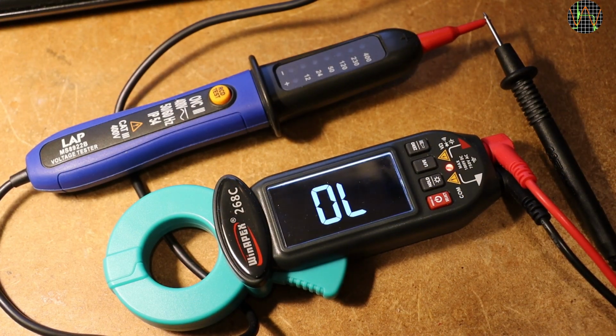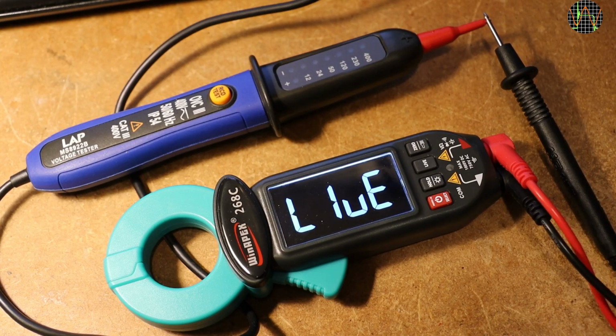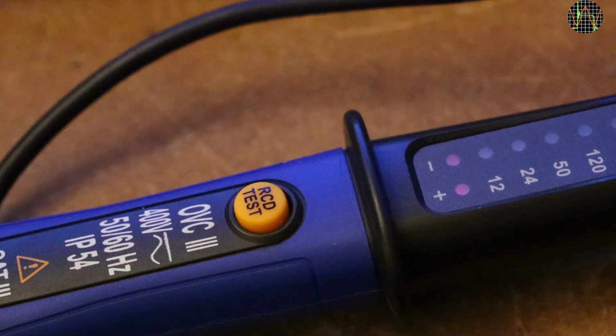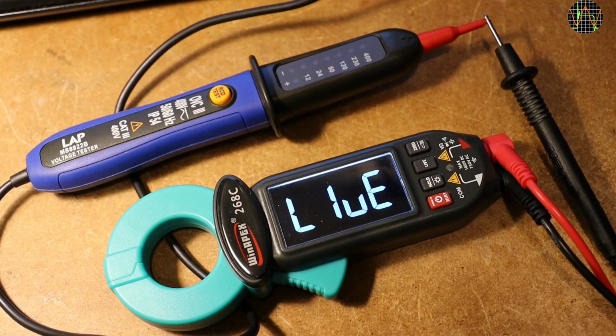I checked if there was anything on the black probe while testing with the red, and if I dim the lights, you can see that the lowest LED of the voltage testers are dimly lit. While that's not dangerous, it relies on the quality of the components in the 268C to remain safe.